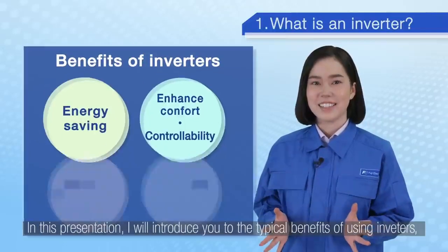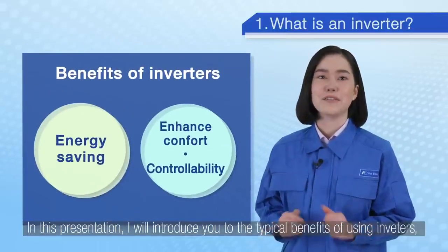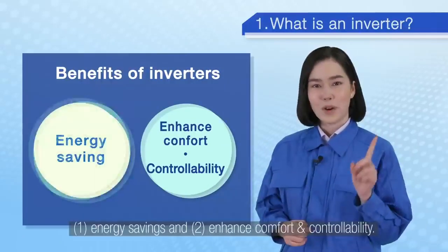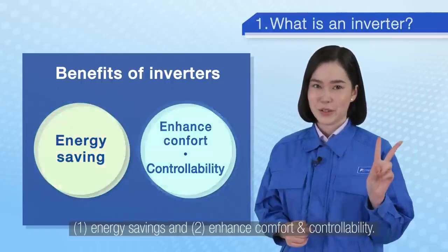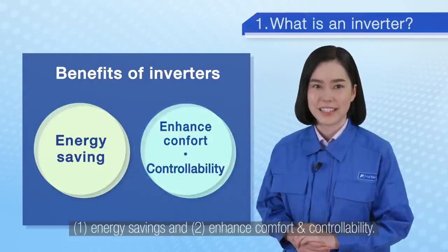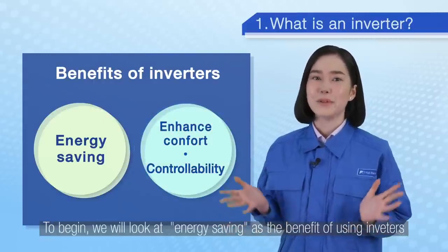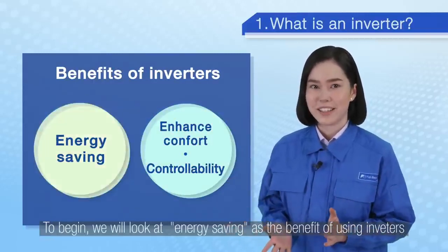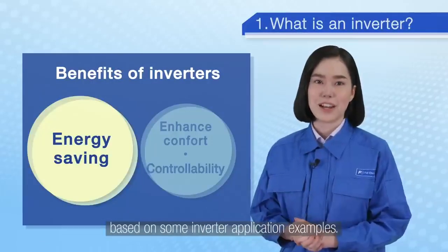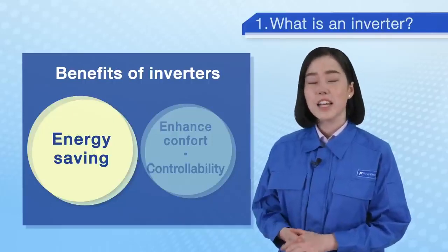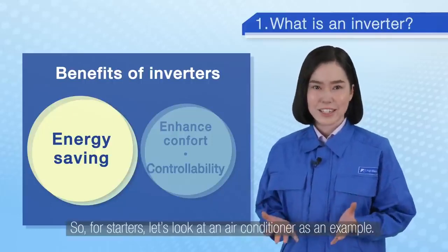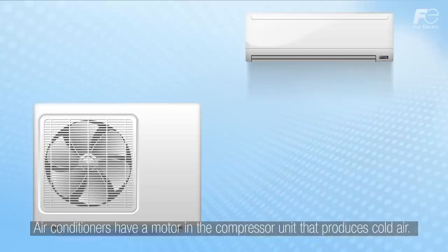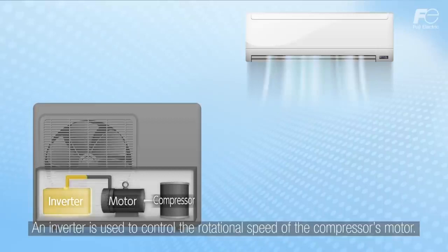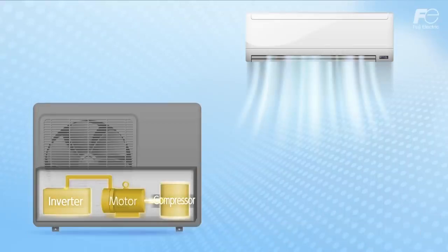In this presentation, I will introduce you to the typical benefits of using inverters. 1. Energy savings, and 2. Enhanced comfort and controllability. To begin, we will look at energy saving as the benefit of using inverters based on some inverter application examples. So for starters, let's look at an air conditioner as an example. Air conditioners have a motor in the compressor unit that produces cold air. An inverter is used to control the rotational speed of the compressor's motor.